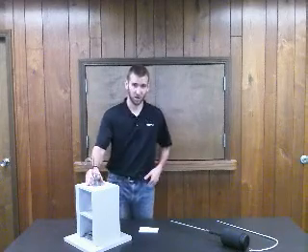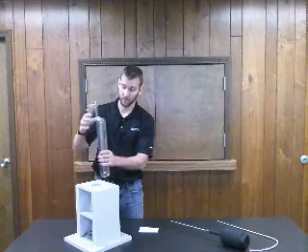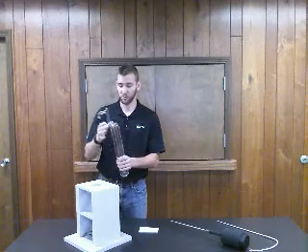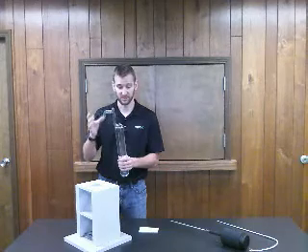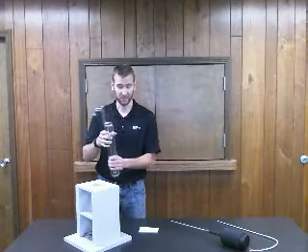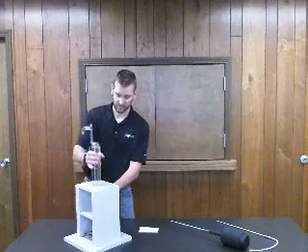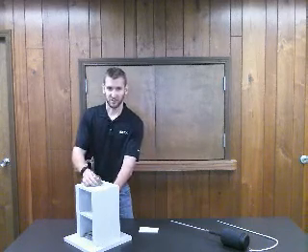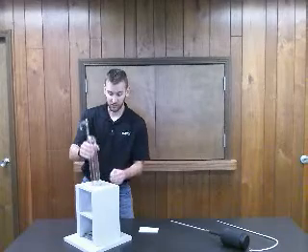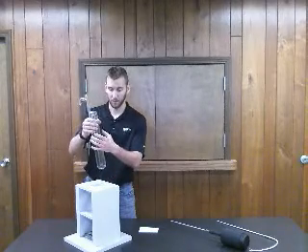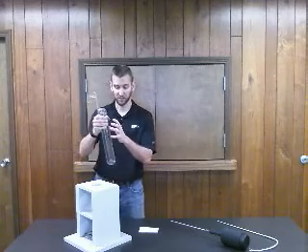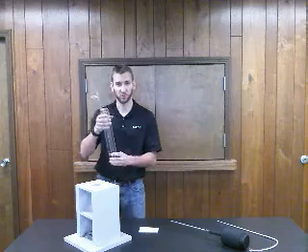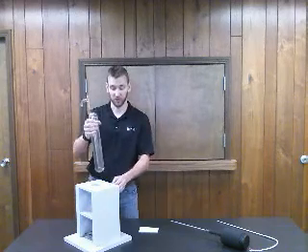What you see here is water and water vapor. The water vapor is up here. Now, all the air was removed during the manufacturing process, so there's almost a complete vacuum in here, but there's still a slight amount of pressure. The ice mantle still needs to be formed around the center well, which will begin forming as the whole temperature of the water becomes a uniform 32.018 degrees.